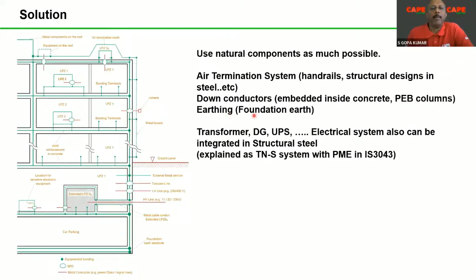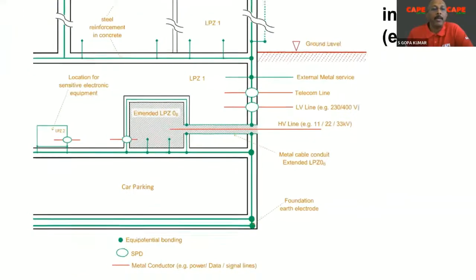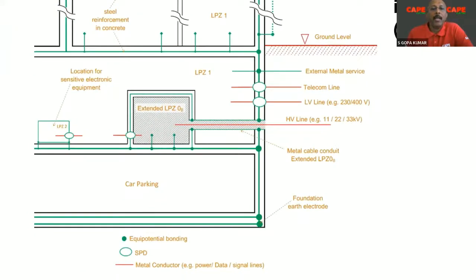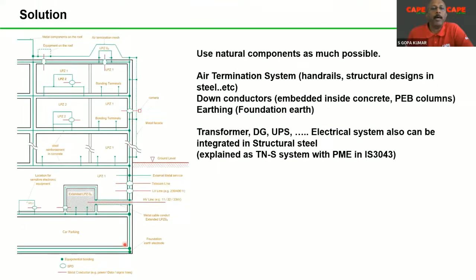Similarly, for earthing, the best method is to use the foundation earth. What is foundation earth? Here you can see, in this particular case, a building with a green line, which is nothing but a conductor embedded inside the concrete foundation of the building. That will do your earth termination system.